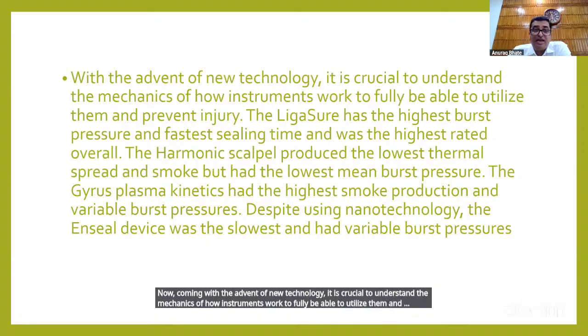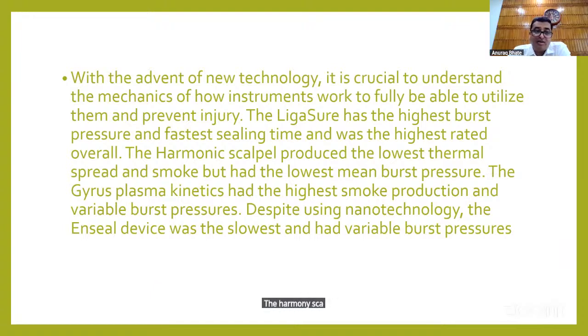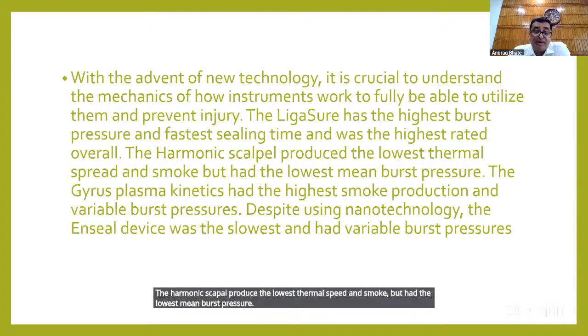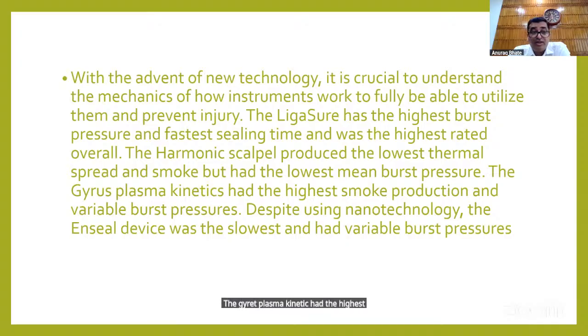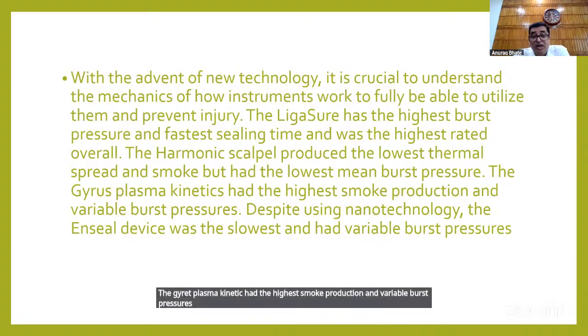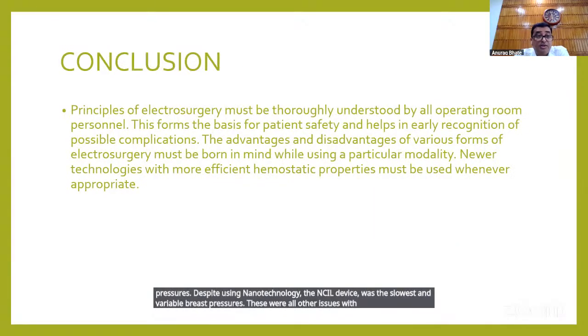The LigaSure has the highest burst pressure and fastest sealing time and was the highest rated overall. The harmonic scalpel produced the lowest thermal spread and smoke but had the lowest mean burst pressure. The Gyrus plasma kinetic had the highest smoke production and variable burst pressures. Despite using nanotechnology, the Enseal device was the slowest and had variable burst pressures. There were other issues with these instruments as well.